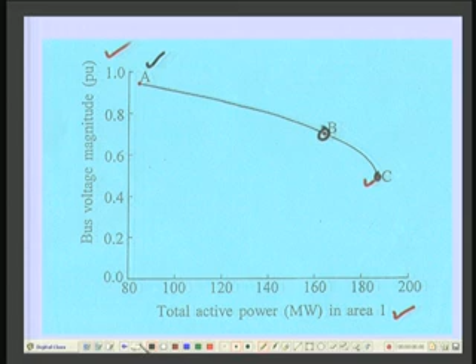Therefore, at this critical point you will find that in the relationship between the Qi and the bus voltage, there is a large portion where the system will become unstable. If we are operating beyond this particular point, then yes, you will be in a position to operate stably. But if you are operating below that particular voltage condition, then you will find the voltage will decrease when you are injecting the reactive power.